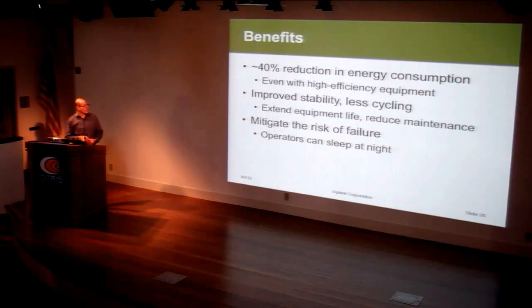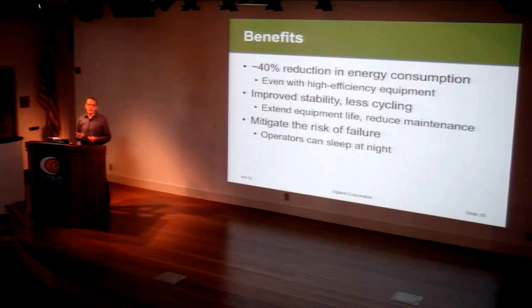But it also mitigates the risk of failure. I mentioned before that instability can manifest as one air conditioner producing cold air that shuts off another one. And if it shuts it off powerfully, the data center temperature might have to rise 10, 15, 20 degrees before it's hot enough at the discharge of the one that's on to allow the one that's off to turn back on.